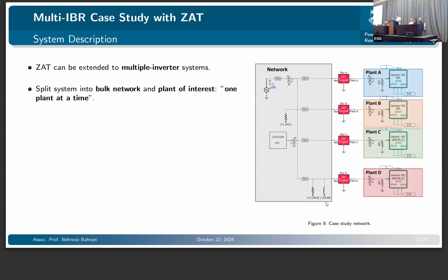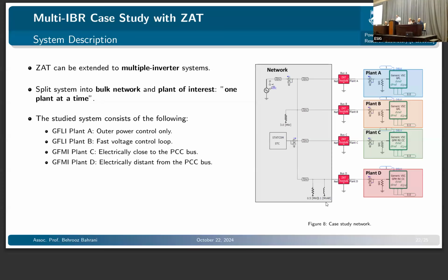So the tool can obviously be applied to SMIB cases, but also to larger systems, multiple inverter systems. In this case, we've got a 4-inverter system. The way to go, obviously, is splitting the system into a bulk network and the plant of interest, one plant at a time. And then you can do different types of stability analysis. In this one, we've got 4 inverters, 2 grid-following, 2 grid-forming. And the rest of the network is a weak connection to the grid with some passive loads and a STATCOM at the point of connection.